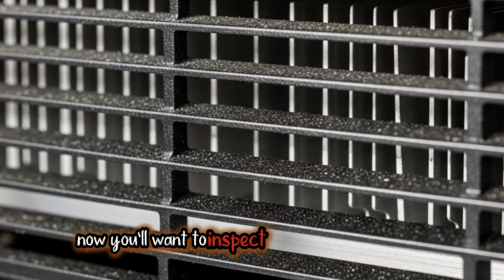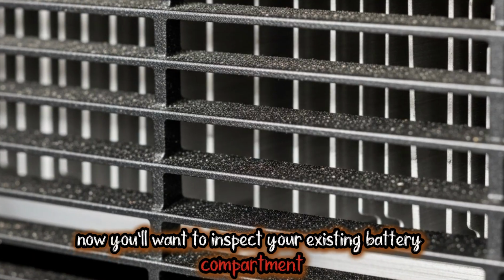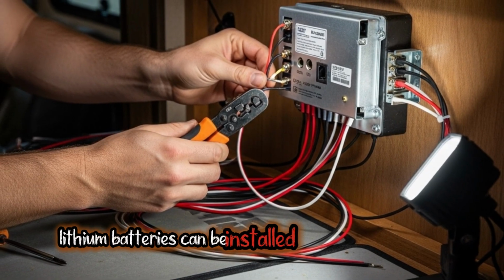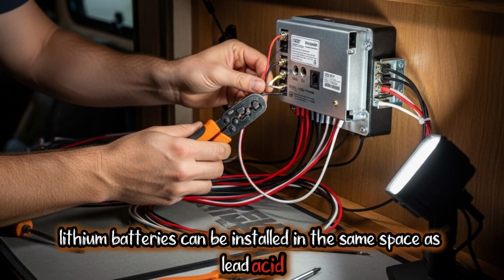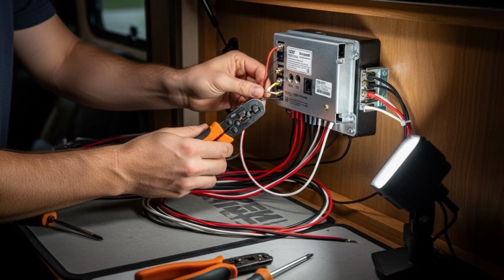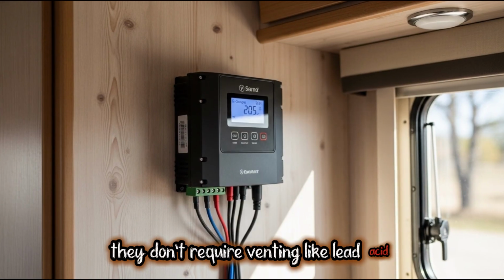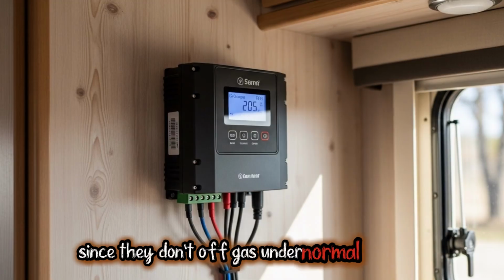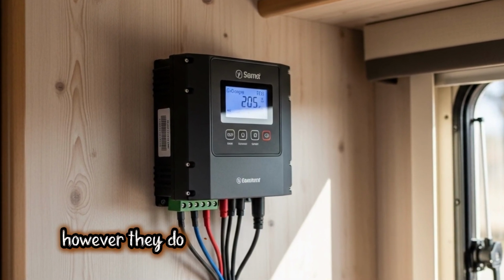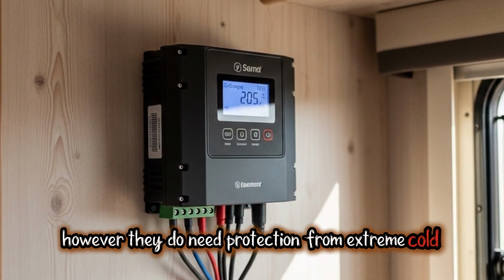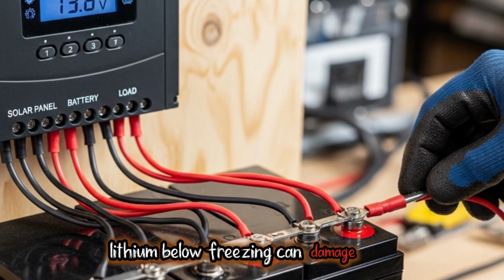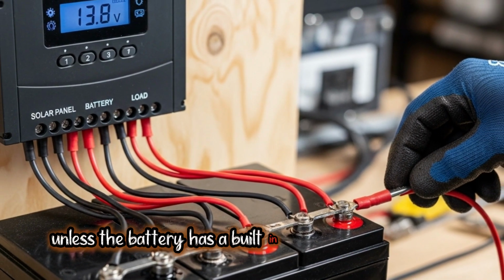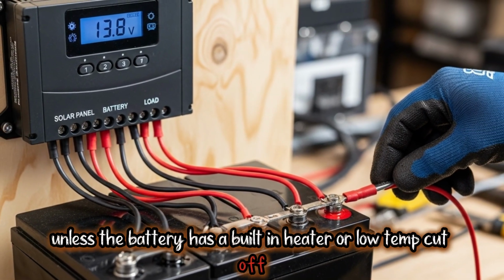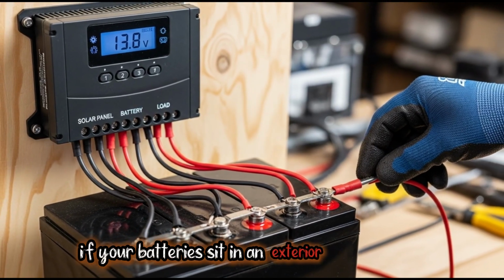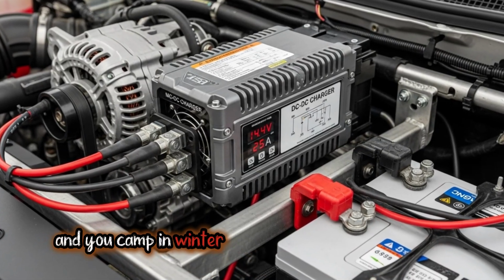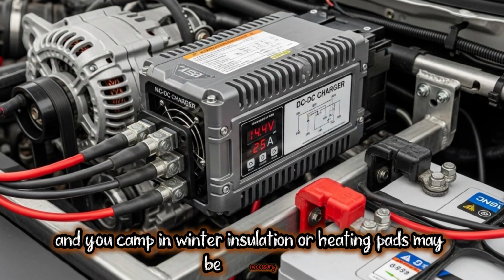Now you'll want to inspect your existing battery compartment. Lithium batteries can be installed in the same space as lead-acid, but there are considerations. They don't require venting like lead-acid, since they don't off-gas under normal operation. However, they do need protection from extreme cold—charging lithium below freezing can damage cells unless the battery has a built-in heater or low-temp cutoff. If your batteries sit in an exterior compartment and you camp in winter, insulation or heating pads may be necessary.